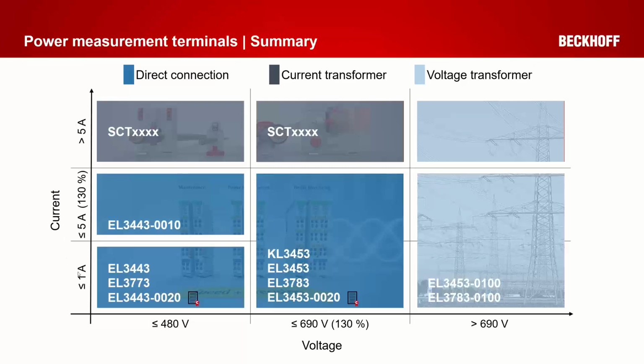Then we come to the different current ranges. We have the 1 amp, which is almost standard, and 5 amp, which is also used for all the applications or maybe high power applications. We have also variants on the 400 volt range and on the 690 volt range. We have a parameter to configure, or as explained for the power terminals, an automatic switch from the 1 amp to the 5 amp range. And above 5 amp, we can offer various split current transformers, which are summarized in our SCT family. In one of my slides, I will explain this family later. So you can see our terminals are prepared to address the wide voltage and current range in all power applications.